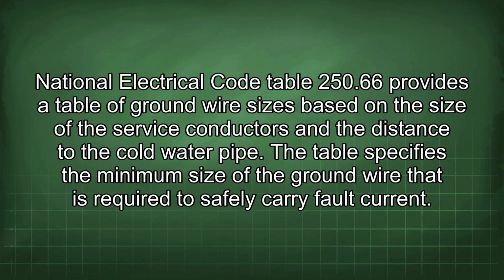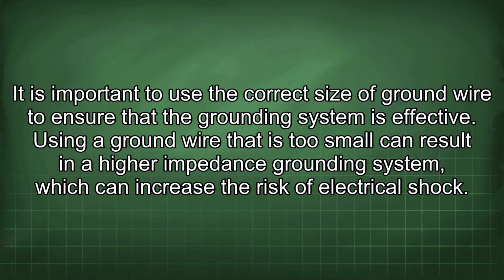National Electrical Code Table 250.66 provides a table of ground wire sizes based on the size of the service conductors and the distance to the cold water pipe. The table specifies the minimum size of the ground wire that is required to safely carry fault current. It is important to use the correct size of ground wire to ensure that the grounding system is effective.